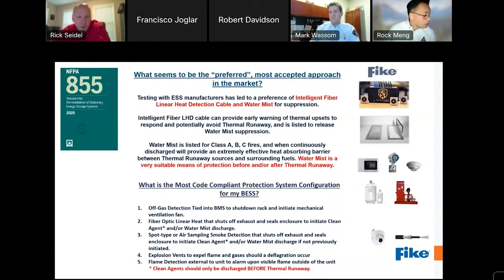What seems to be the preferred or most accepted approach in the market, with the full-scale testing that Fike Corporation has done with some ESS manufacturers, the obvious choice and the best preference and level of performance has been intelligent fiber linear heat detection cable partnered with a water mist system for suppression. Water mist has proven to be a suitable means of protection before and or after thermal runaway in absorbing the heat and trying to block the radiating heat and keep the temperature low on all surroundings as best as possible.